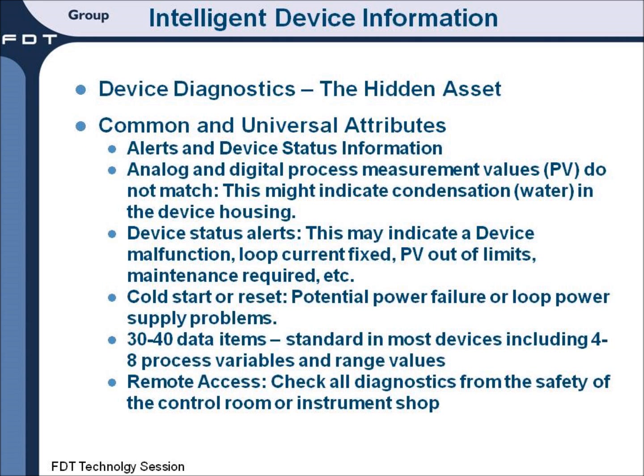What does this intelligent device information look like? The information falls into two categories: one, common and universal attributes; and second, device-specific attributes. In the case of common and universal attributes, these are alerts and device statuses that give you a quick idea as to whether or not there's a potential problem — alerts such as a device malfunction, that the loop current might be fixed, someone might have left it in that position by accident, or that the process variable is out of limit, or that there was a cold start or reset indicating possibly a loss of power. In most cases there are 30 to 40 data items available for your review to be able to determine whether there's a problem.